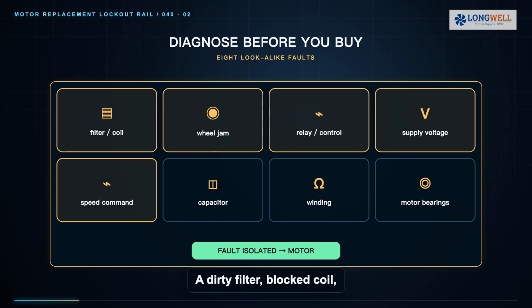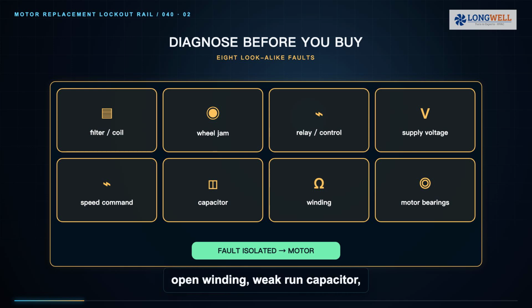A dirty filter, blocked coil, jammed wheel, failed relay, damaged control board, open winding, weak run capacitor, low supply voltage or incorrect speed command can produce similar symptoms. Identify whether the unit uses a permanent split capacitor motor, an electronically commutated motor, or another architecture. Measure only with instruments and procedures appropriate to the equipment. Do not buy a motor from symptoms alone.